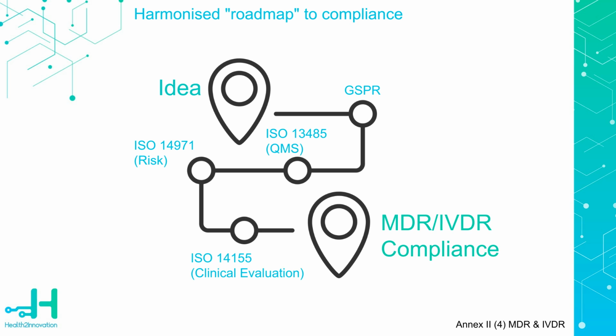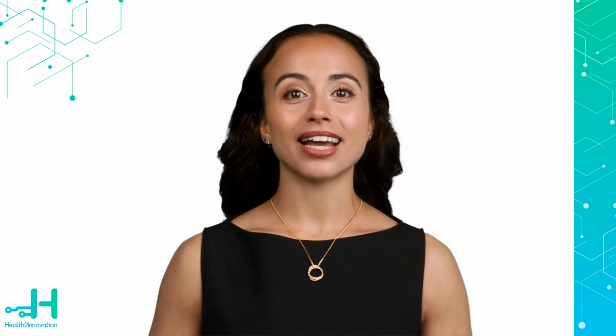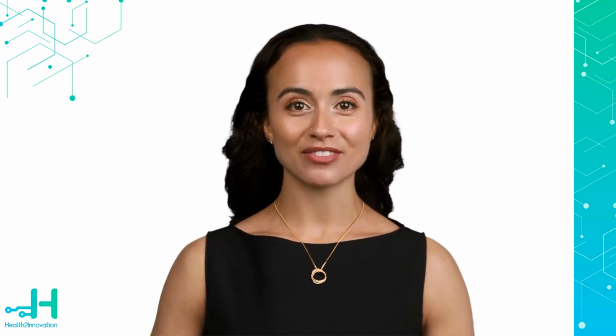In our example, this would mean data from software testing and clinical validation studies demonstrate the app's accuracy and reliability in detecting irregular heartbeats. We will include preclinical and clinical data, with test results and clinical evaluation reports signed and released. Getting a product to market and keeping it there is clearly a lifetime commitment, at least as far as the product technical documentation is concerned.